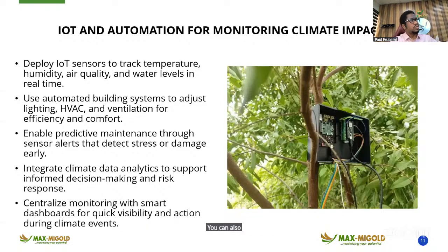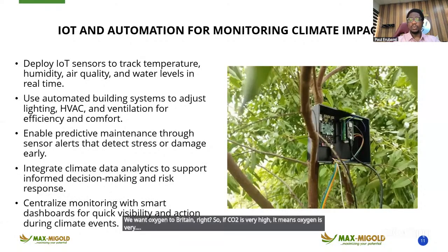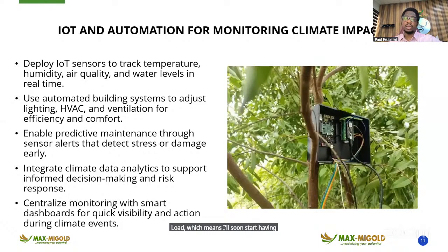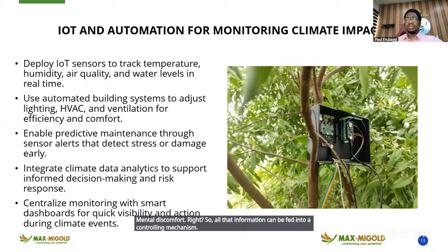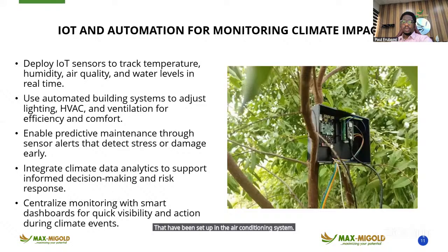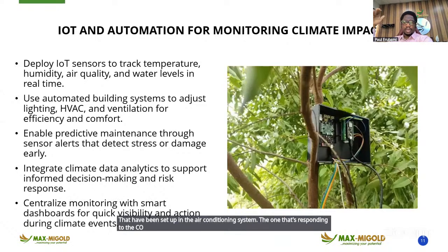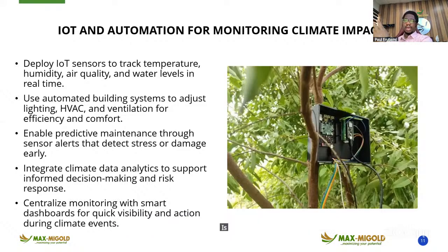You can also feed in a sensor that monitors CO2—the air we breathe out, while we want oxygen to breathe in. If CO2 is very high, oxygen is very low, and I'll soon start having headaches and other mental discomforts. That information can be fed into a controlling mechanism in the air conditioning system that responds to CO2 levels by controlling the fresh air intake dampers—opening when CO2 is very high to enrich the space with fresh air, then closing and continuing to monitor.